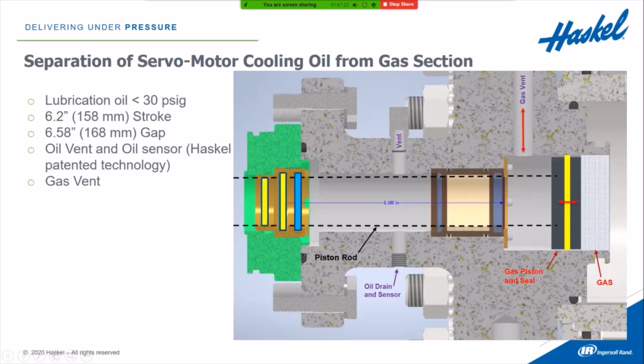We have another vent right here in our distance piece. So if there is any gas that does get into this section, it will be vented out to atmosphere there. And then if any oil does get across the oil seals here, it will be collected in this oil drain, and there's a sensor here that will notify the control that there is oil where there shouldn't be.